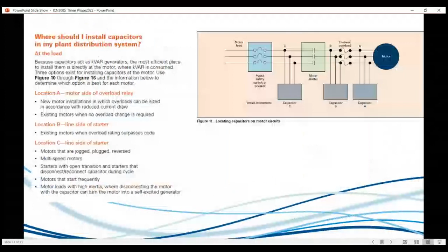So reverting into that, I might ask this as a bonus question. Who knows? The question is, where do we install these capacitor banks to correct the power factor? They state there, because the capacitors act as kVAR generators, that's essentially true. The most efficient place to install them is directly at the motor, where the kVAR is essentially consumed.